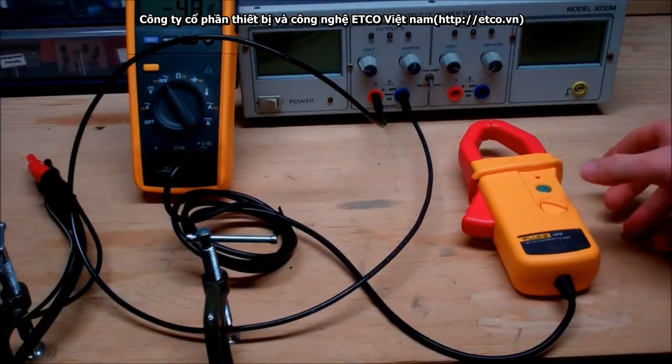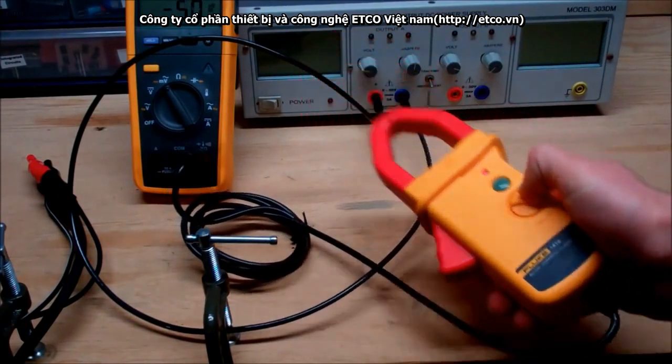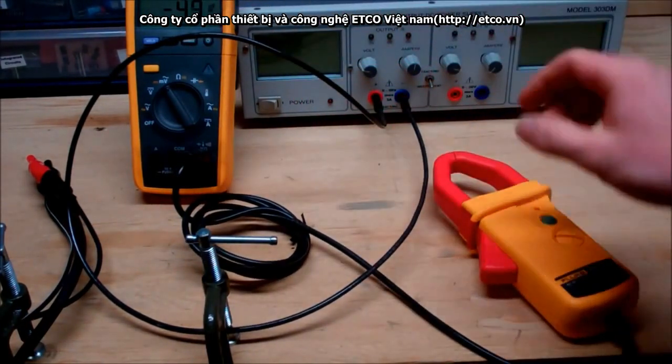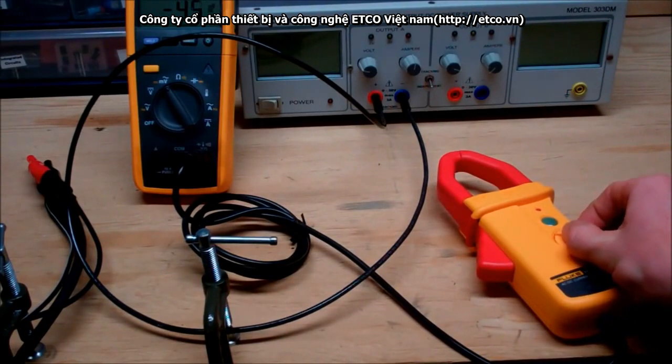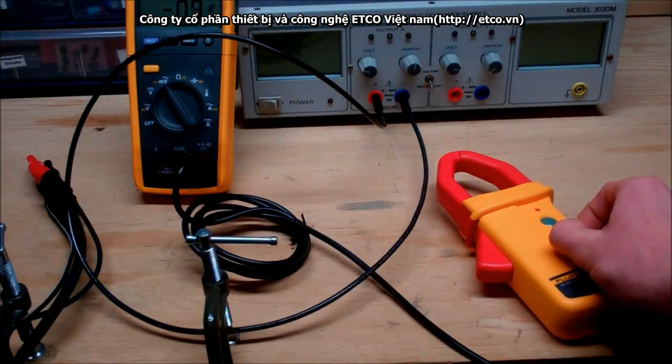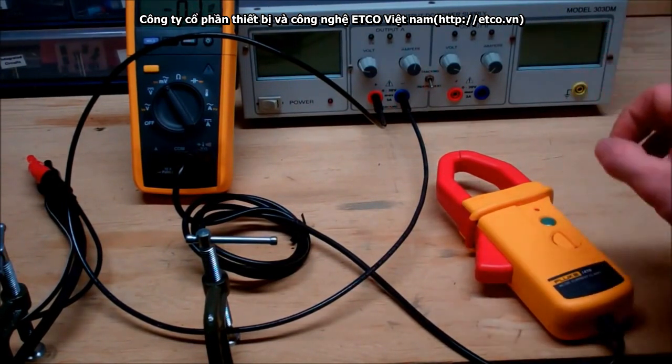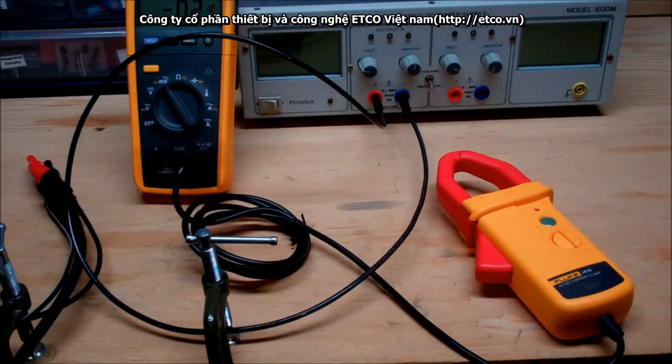Now, in order to take a DC measurement, what we're going to do first is turn this on. Then, as you can see on the display screen right here, we have a negative reading of millivolts. So that just means we have to adjust this until we have a zero reading. So it's just a quick little calibration and it works fairly well. When you get onto your higher accuracy meters, there's a lot of distortion. And this is only for the DC as you're only using the Hall effect for DC measurements.